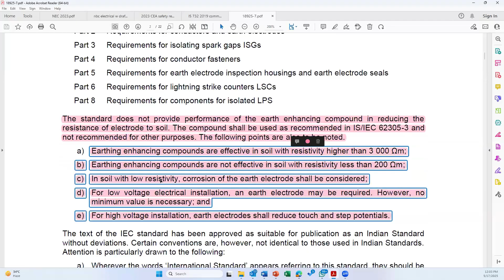Earth enhancing compounds are not effective in soil with resistivity lesser than 200 ohm meter. In soil with low resistivity, corrosion of the earth electrode shall be considered. These requirements are very much modified, but still a little bit of improvement in this area is required.